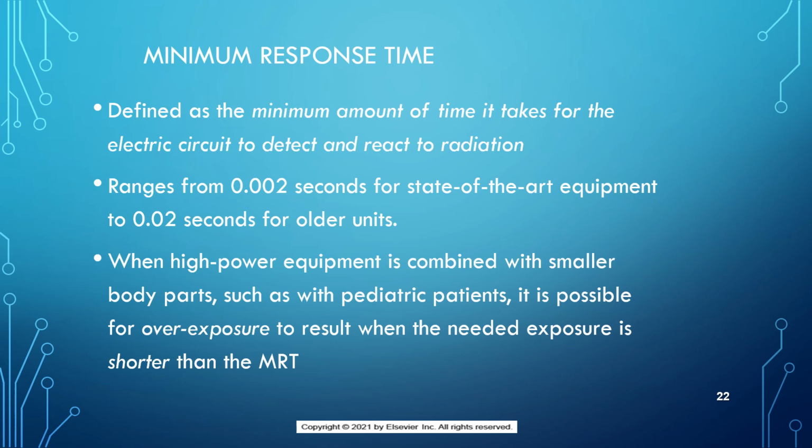And so when your exposure times are really, really low, like in the hundredths of a second range, the AEC loses its ability to deliver an optimal exposure time. So this is a special consideration for pediatric patients.